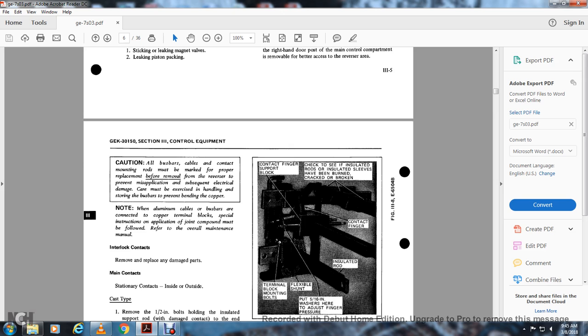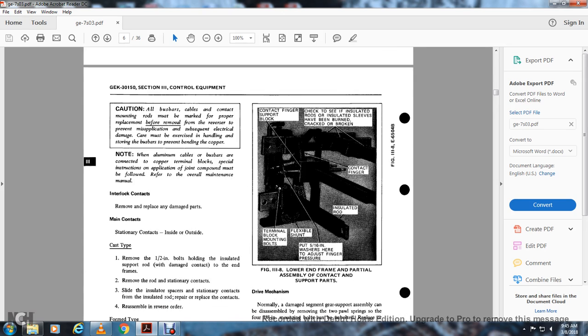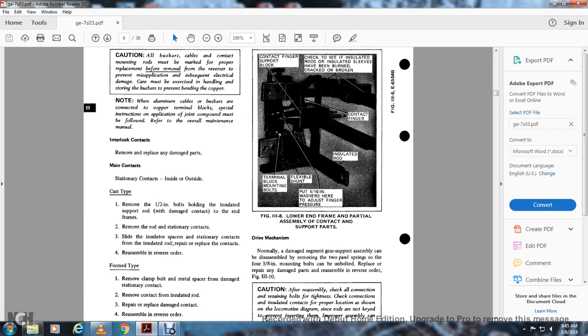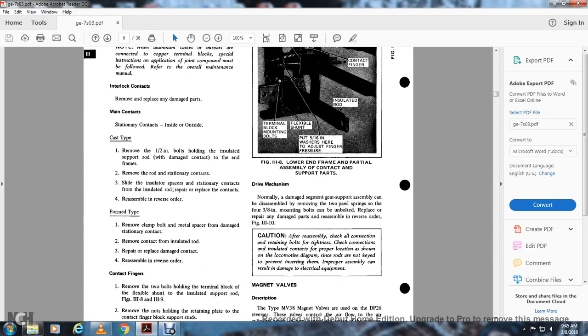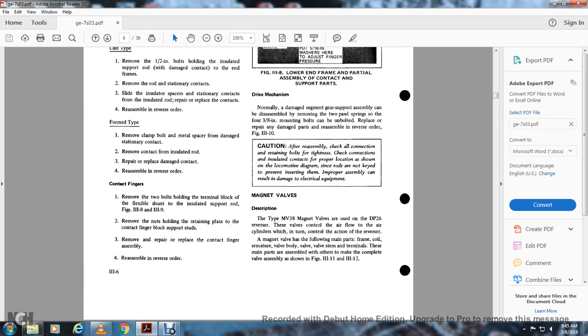Interlocking contacts: remove and replace any damaged parts. Main contacts, stationary contacts, inside and out. Cast type: 1. Remove the 1/2-in. bolts holding the insulated support rod with the damaged contact at the end of the frame. 2. Remove the rod and the stationary contact. 3. Slide the insulator spacer and stationary contact off the insulated rod. Repair or replace the contacts. Reassemble in the inverse order.